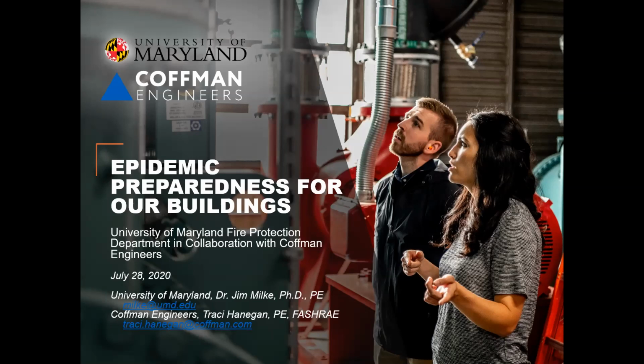So another one is sort of related to filters, but it's UV lamps, their use, and if you would put them upstream or downstream of filtering. So the UV lamps, there's a few different ways to do that. The in-room UV, upper room UVGI can be pretty effective. It's been well proven for years for things like tuberculosis. So that's one option, and you don't have to have real intense bulbs. The effectiveness of UV is partly the contact time and partly the intensity of the bulb, and there's an equation to figure that out. So if you have upper room UVGI where that light's going all the time and air is circulating through a space, the bulb intensity level can be pretty low and the power requirements can be pretty low because that air is going to be moving by slowly and have a lot of time to be exposed to that light.